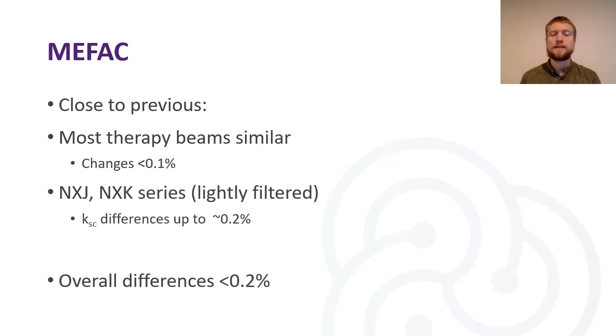For the MEFAC again, the updated values are fairly close to the previous values. For most of the therapy beams, the changes are less than 0.1%. We have the NXJ and NXK series, which are very lightly filtered beams, and we do see some scattering differences there in the order of 0.2%. Overall, we see differences of less than 0.2% for the therapy calibrations that we offer.